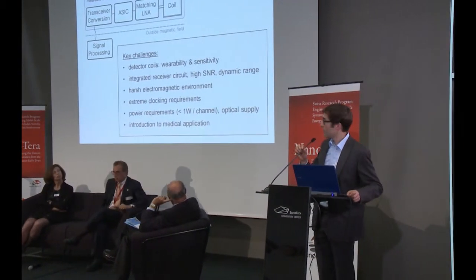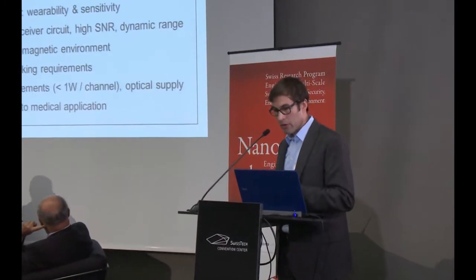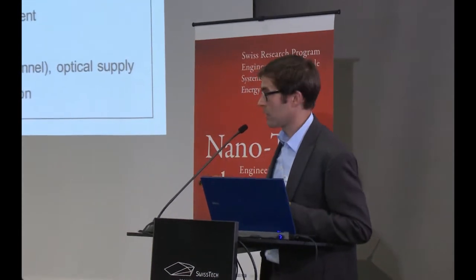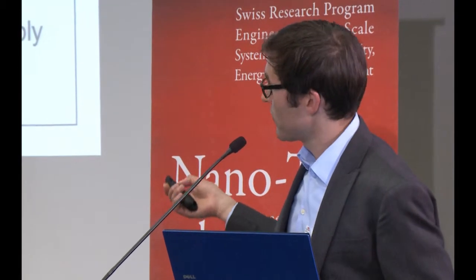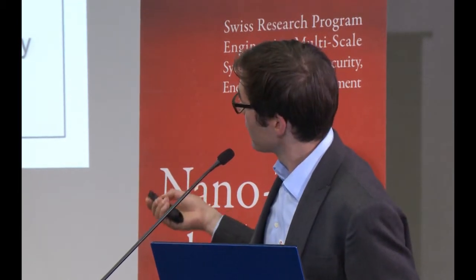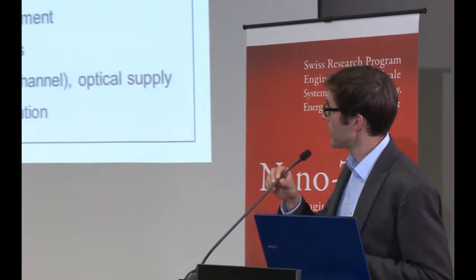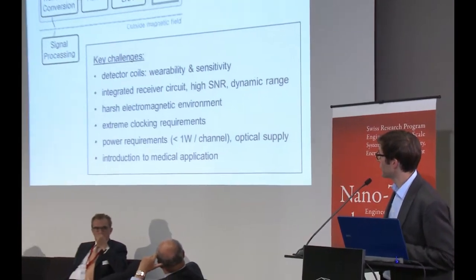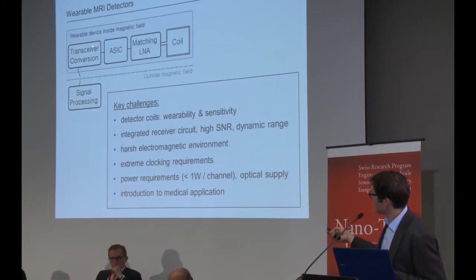What does the project encompass? Well, first of all, it's about building a coil that is flexible and matching the body. After this coil, of course, we need some electronics, since we need to match and tune the coil to get the best performance out of it. Then, having the coil tuned and matched, the signal will be digitized in an ASIC built by the Institute for Integrated Systems.